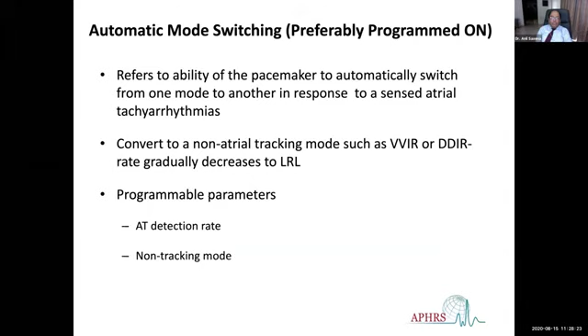So when we have a DDD, it means that both chambers are paced and both chambers are sensed as well, and the third letter D means a dual response: atrial inhibited, ventricular triggered. So when it senses an atrial signal, it will inhibit pacing in the atrium and trigger pacing in the ventricle. In a DDI mode, it will just inhibit, it will not trigger any pacing in the ventricle. So the rate will be whatever low rate is programmed. And when the patient does activity, the rate will increase accordingly. So even if the patient is having atrial fibrillation, the patient will pace at the lower rate of 60 if we have programmed 60. And when the patient does activity, it will gradually increase to 65, 70, 75, 80, whatever. So that is the meaning of DDI. It's a non-tracking mode, and DDD is a tracking mode. That is, it tracks the atrial activity and paces the ventricle.